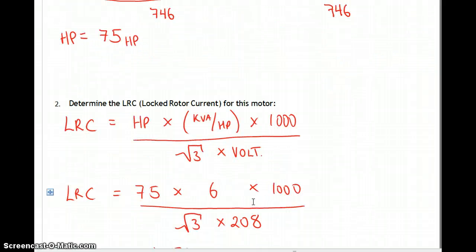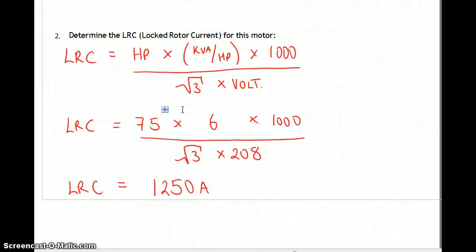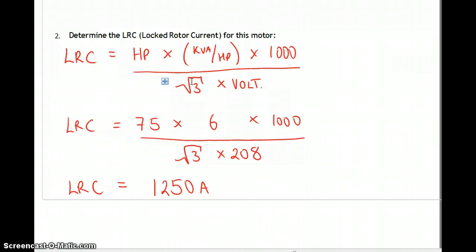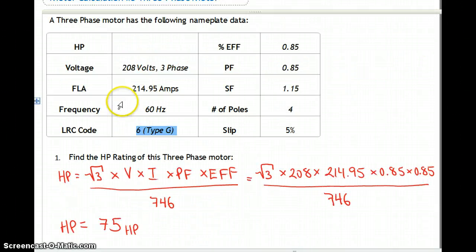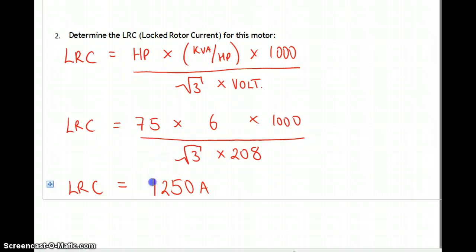Locked rotor current: 75 horsepower times 6 times 1,000 over root 3 times 208 — don't go on cruise control, this is three-phase so you need root 3 times 208. The locked rotor current is 1,250 amps. Normally it pulls 215 amps; locked rotor current is 1,250 amps.